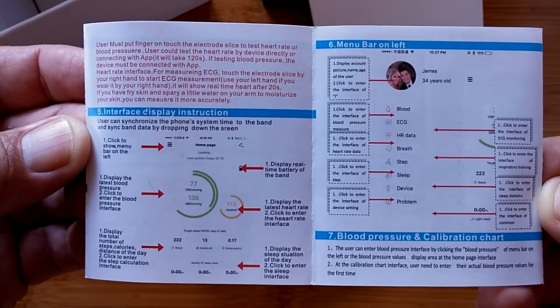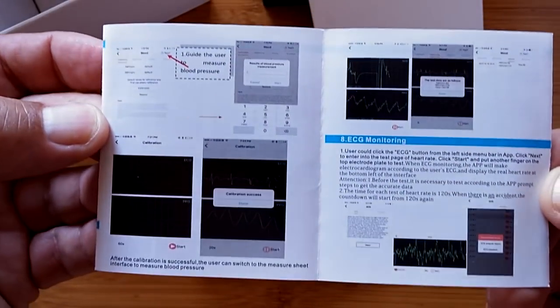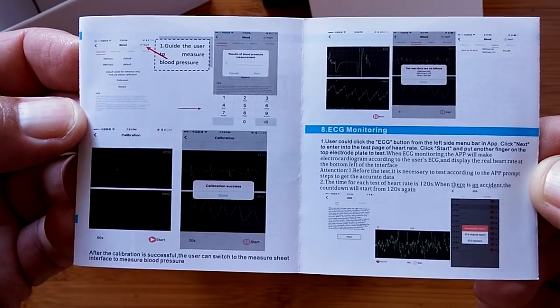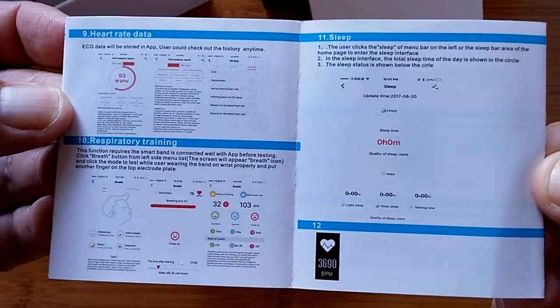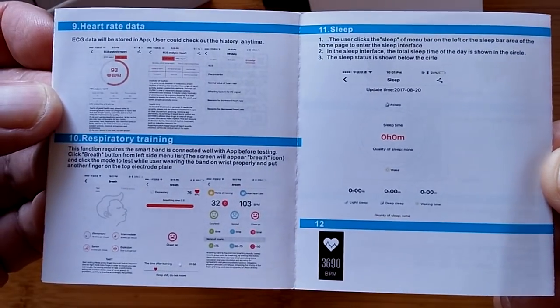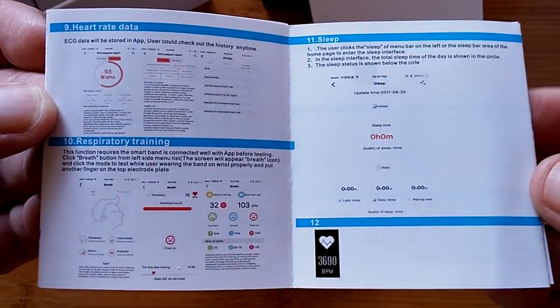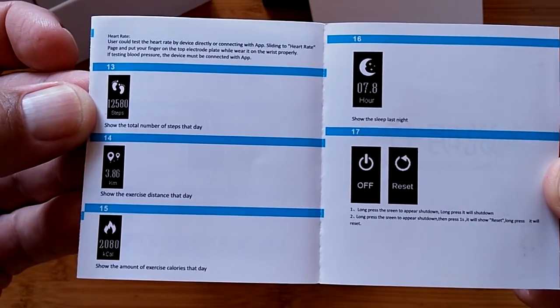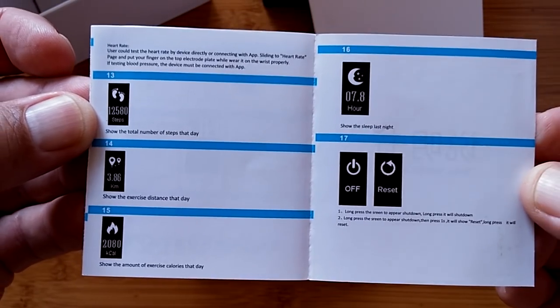There's the menu and instructions on how to do the blood pressure reading and calibration. The more sophisticated devices have the ability to calibrate to your specific situation - if you tend to have high blood pressure, you can calibrate by doing a measurement and set the band to equate to your normal reading. Then look at readings as deviations from that norm, giving you higher accuracy.